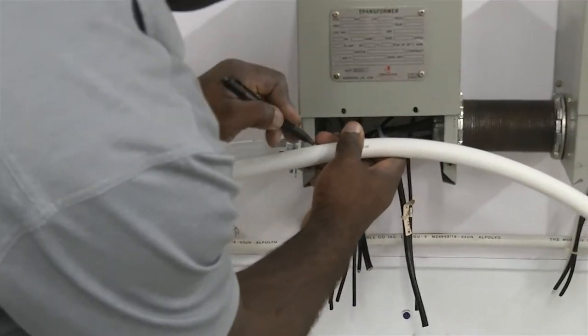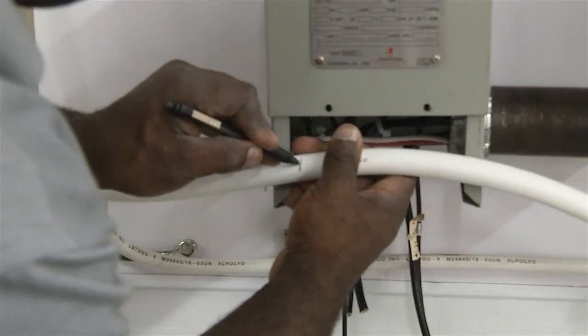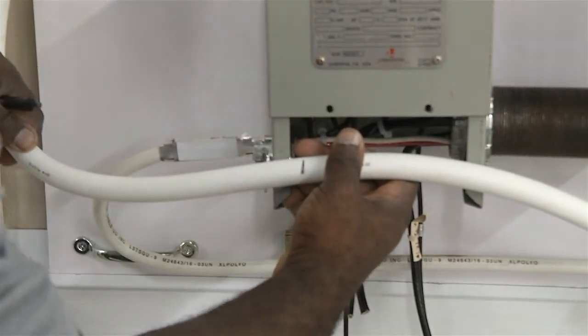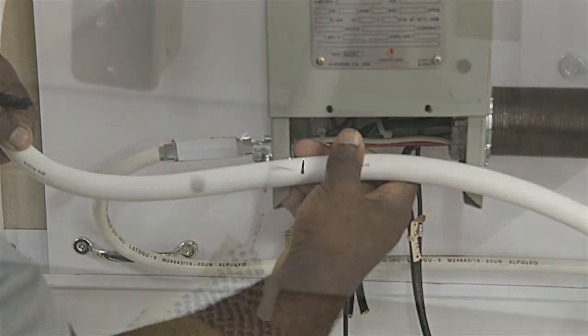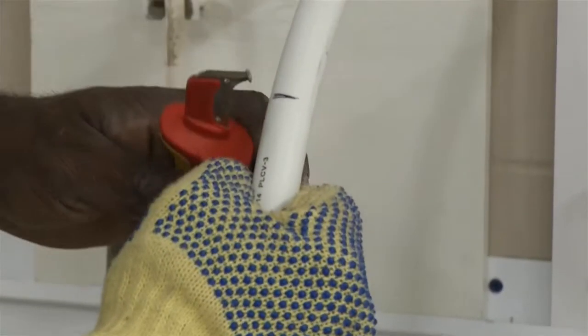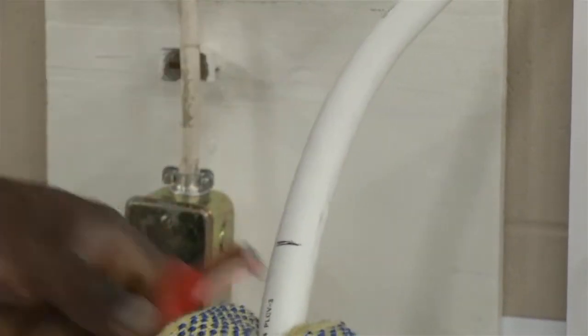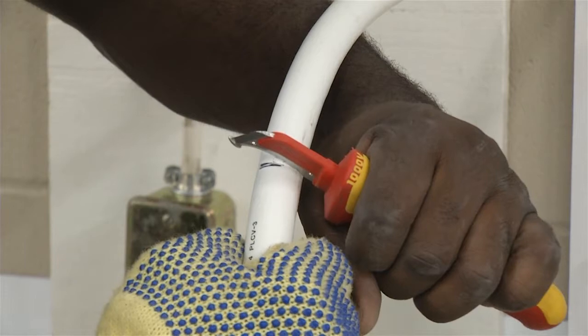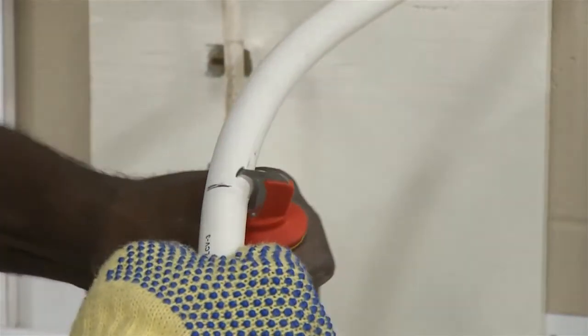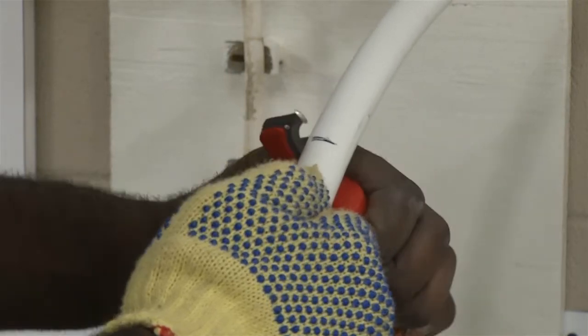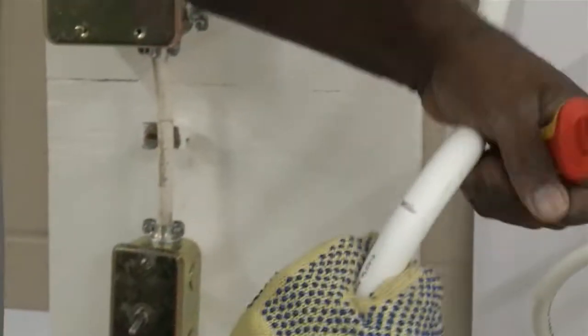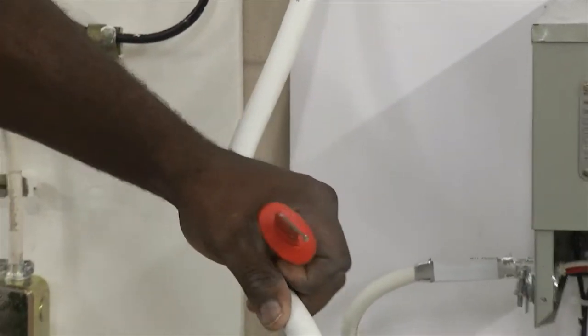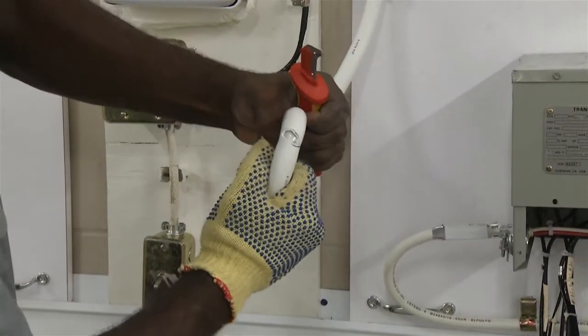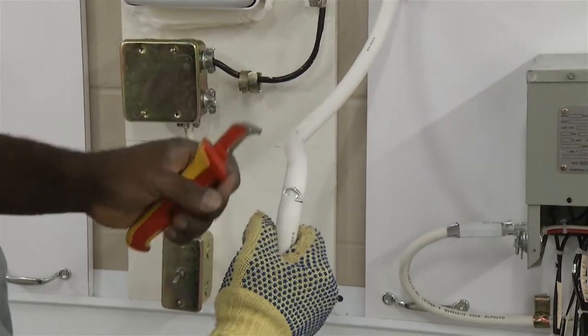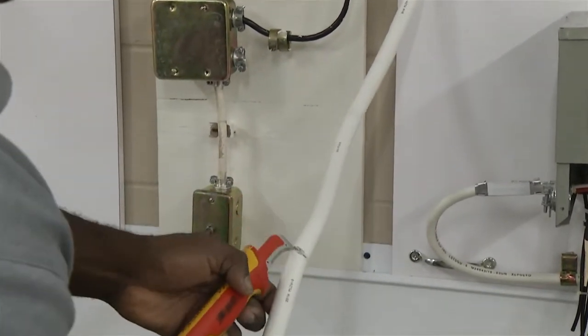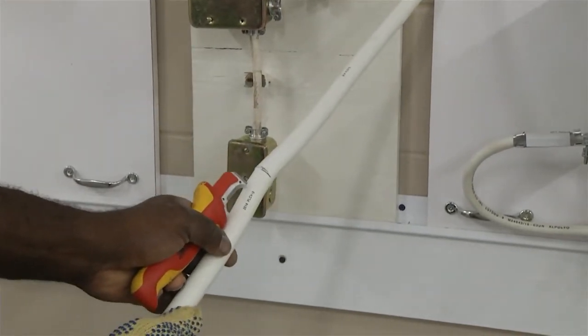Mark the cable to ensure that 1/8 inch is left inside the panel after the jacket is cut. A Kevlar glove is required on the hand that is holding the cable when cutting. Cut through the jacket, but be careful not to cut the conductors. Place the flattened end of the hook bill knife or cable stripper on the jacket edge and remove the jacket.